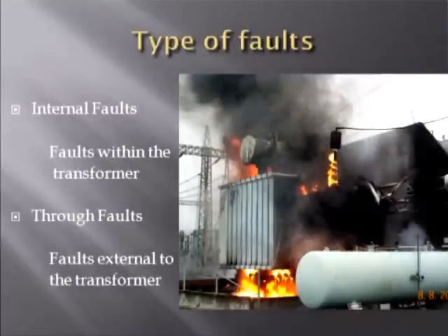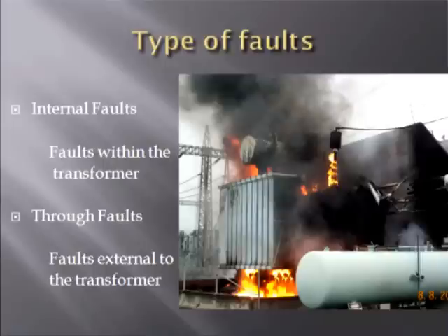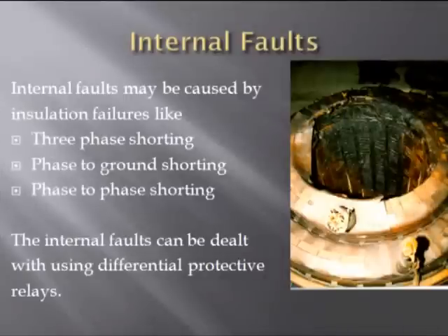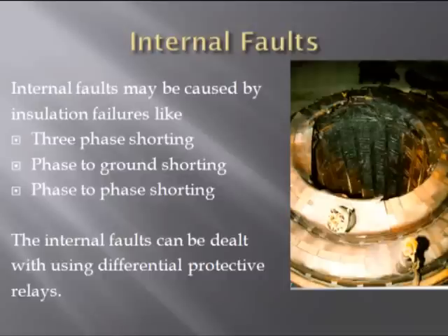Transformers are prone to two types of fault: internal faults that occur within the transformer proximity, and through faults that occur external to the transformer. Both these faults may cause a very large current to flow in the circuit, which may damage the insulation and hence damage the system. Faults that occur inside the transformer, called internal faults, may be caused by insulation failures like three-phase shorting, phase-to-ground shorting, and phase-to-phase shorting.